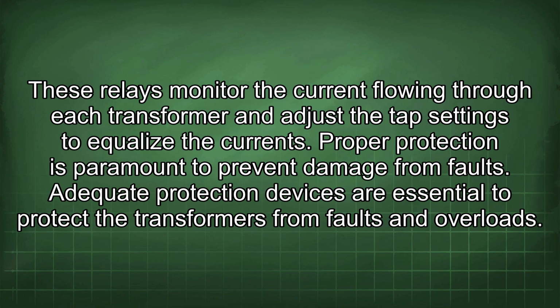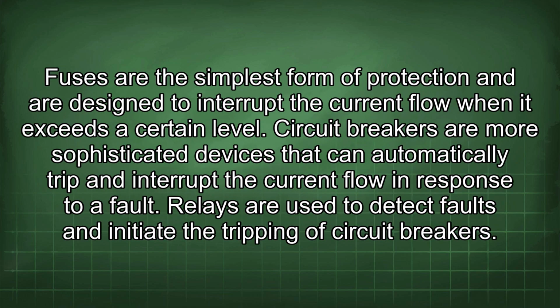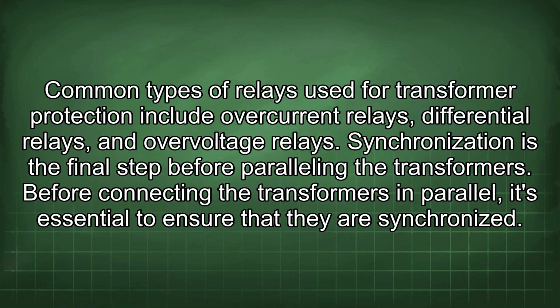Proper protection is paramount to prevent damage from faults. Adequate protection devices are essential to protect the transformers from faults and overloads. Fuses are the simplest form of protection and are designed to interrupt the current flow when it exceeds a certain level. Circuit breakers are more sophisticated devices that can automatically trip and interrupt the current flow in response to a fault. Relays are used to detect faults and initiate the tripping of circuit breakers. Common types of relays used for transformer protection include overcurrent relays, differential relays, and overvoltage relays.